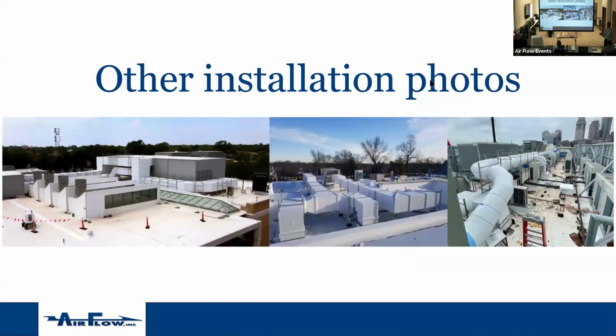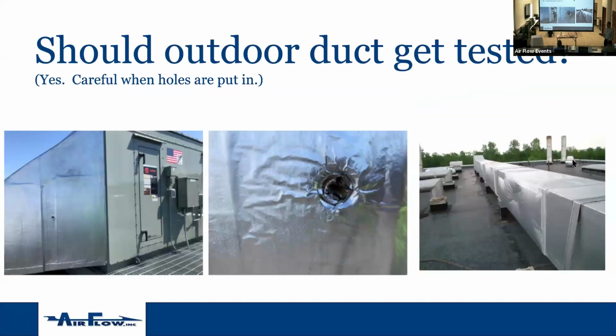Okay, yeah, some installation photos. Back to this picture, this is telling us, even though that's high pressure ductwork, and every contractor knows how to make high pressure ductwork really well and how to seal it, this is a brand new install and it is clearly bubbling out. What's bubbling out? It's bubbling between the insulation, this is the peel and seal stuff. So it's pushing the insulation away, right? And it's got to get through that peel and seal somehow. Now it's holding it, but is it in the ductwork anymore? It's not. So we've leaked some.